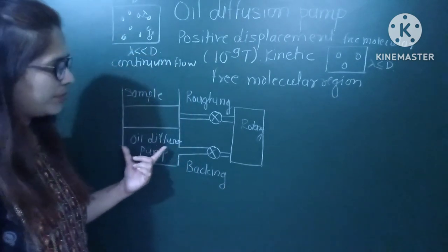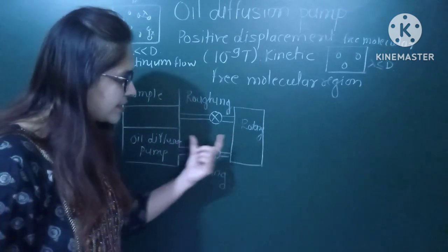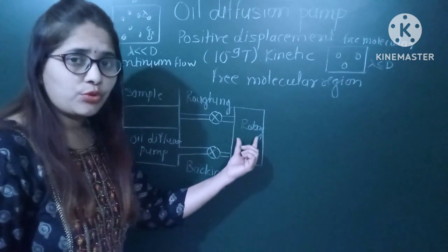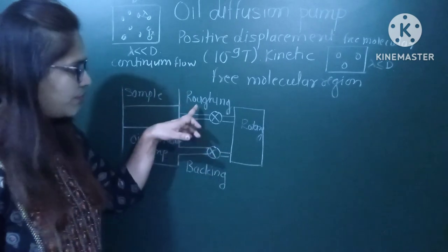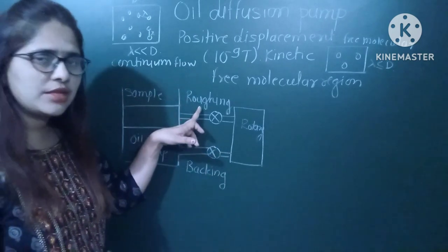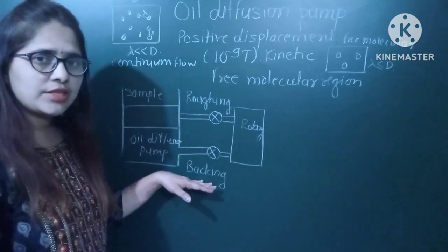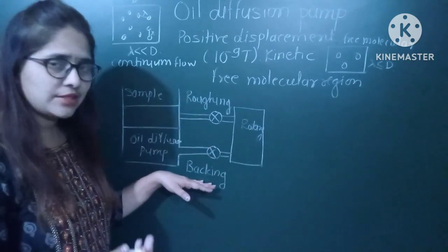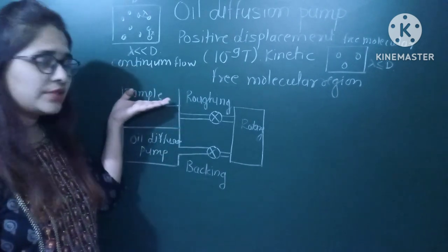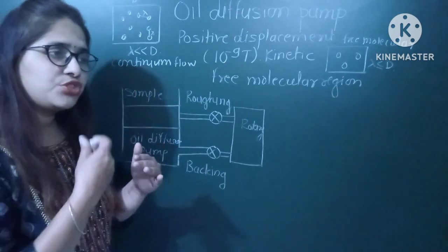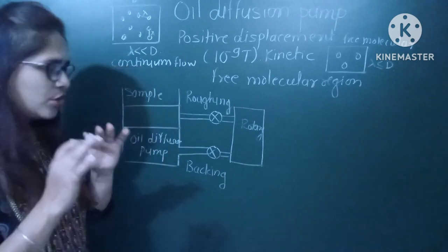The oil diffusion pump is connected to the rotary vane pump by two different valves. The first is called the roughing valve and the second is called the backing valve. This is the sample chamber where we want to generate the vacuum.